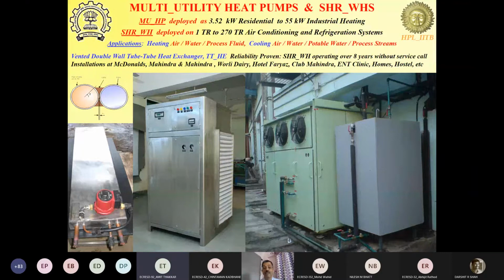Not only that, we were also able to reduce the noise of this system significantly, because a conventional 24-ton air-cooled system would have much larger fans. Compared to the air-cooled system, the total fan power consumption in our system reduced by 9 times. That was partly because much lower airflow power was required, and the pressure drop through our contacting device was less than 1 mm of water column. That is just 10 pascal, compared to around 100 to 150 pascal through most air-cooled condensers.